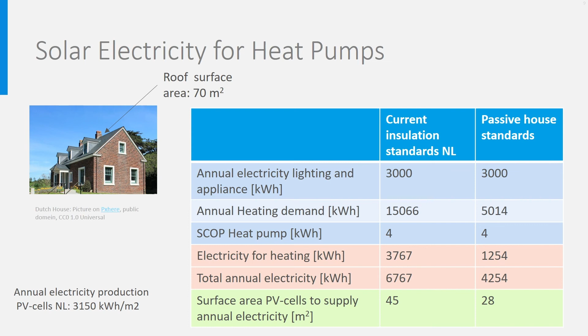We now want to place PV cells on the roof. Modern PV cells have an electrical annual production of 150 kilowatt-hour per square meter in the Netherlands. So in the well-insulated version, we need 45 square meters of PV cells, and in the passive house version, a bit more than 28 square meters, which is very well feasible. It is not because the PV cells are producing annually the same quantity of electricity as needed by the heat pumps, lighting and appliances that no electricity from the grid will be used.